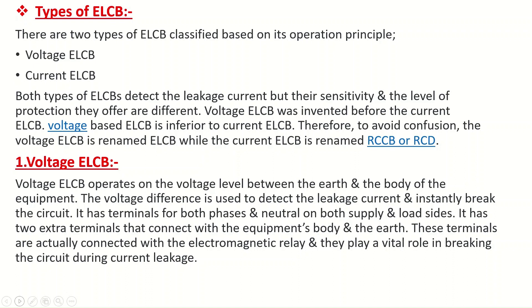Voltage ELCB operates on the voltage level between the earth and the body of the equipment. The voltage difference is used to detect the leakage current and instantly break the circuit. It has terminals for both phase and neutral on both supply and load sides, plus two extra terminals that connect with the equipment's body and the earth. These terminals are connected with an electromagnetic relay and play a vital role in breaking the circuit during current leakage.